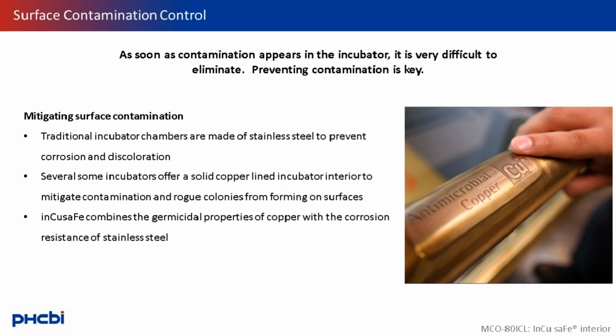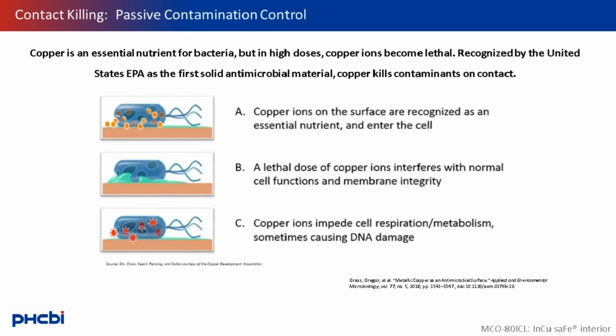A third option was created to exploit the benefits of both types of metal. While overcoming the issues associated with corrosion, a stainless steel copper alloy provides both the antimicrobial benefits of copper, as well as the strength and the corrosion resistance of stainless steel. As a result, an incubator with a stainless steel copper alloy interior combines the germicidal benefits of copper with the corrosion resistance of stainless steel. Bacteria, yeasts, and viruses are rapidly killed on metallic copper surfaces, and the term contact killing has been coined for the process.